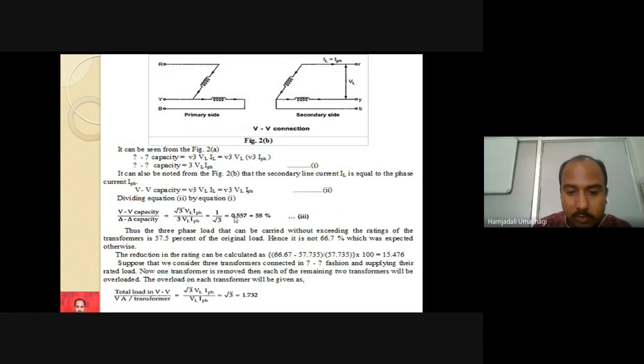So 1 by root 3 is equal to 0.577. This is not 0.55, this is 0.577. In percentage it will be 57.7, which is approximated to 58%. So once the connection changes from delta-delta to open delta, it can carry the load safely at 58%. You cannot connect 100% of the load like earlier in the delta-delta system. You need to reduce the load, and that reduced load should be 58% of the previous load, so that it can carry it very safely.